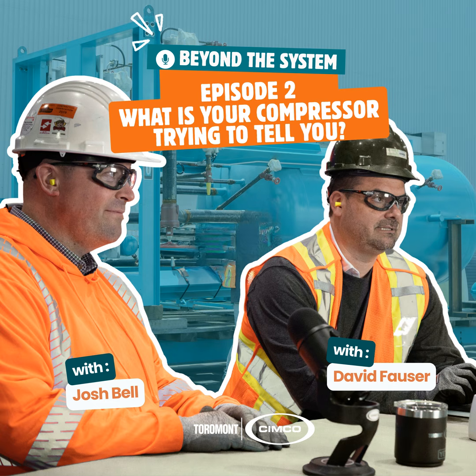I've been on a call multiple times where the base wasn't constructed well enough, and here we are 30 years down the road, and they've got massive vibration in their compressor room, and it's just the stress of time and vibration that has finally cracked the steel base. And here we are, luckily without an ammonia leak or a refrigerant leak, and we're just welding the base back together. Then you start to consider: wow, all the movement that just happened, what else did it affect? Did it affect the valves, flanges? Did something come loose in the system? It's just all those things that might not seem like a high percentage of happening, but they could.